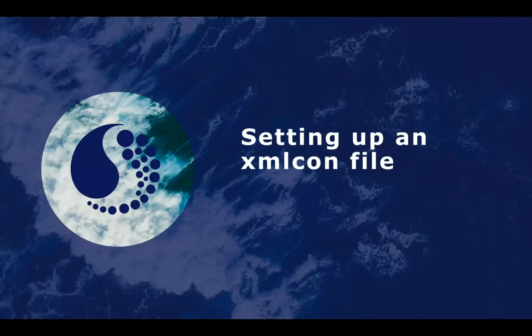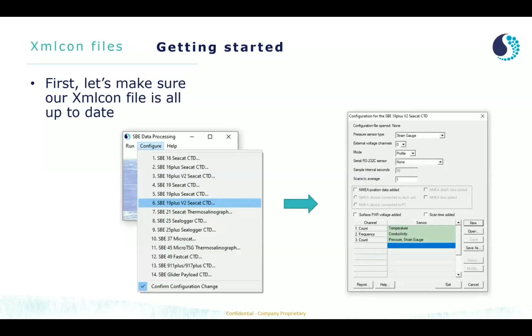So first, let's talk about setting up an XMLCON file and what they actually entail. An XMLCON file is the file you're going to use to input into the conversion software, to make sure the software knows specifically what external sensors and what calibration coefficients we have for our instrument. It's important we get this right, otherwise our data might be a bit off, or we might not even get any data for some of those external voltage sensors if we don't specify them via an XMLCON file.